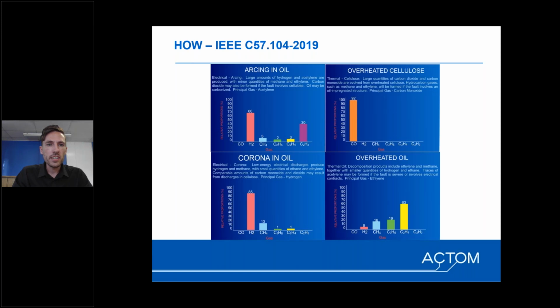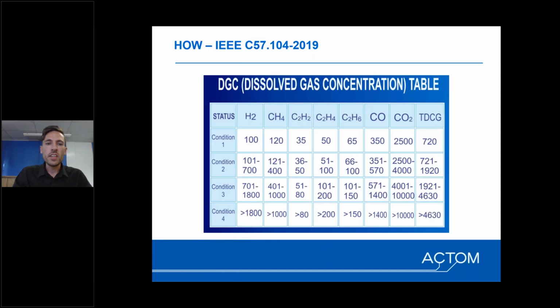Just a little bit more about that IEEE standard. With the different gas levels inside the transformer, we can see when a potential problem is going to arise. Depending on which gas is more prominent, or which ratio is higher than the other, we can intelligently say that that is the problem. The dissolved gas concentration, depending on which condition it falls under, gives us the actual severity of the problem.